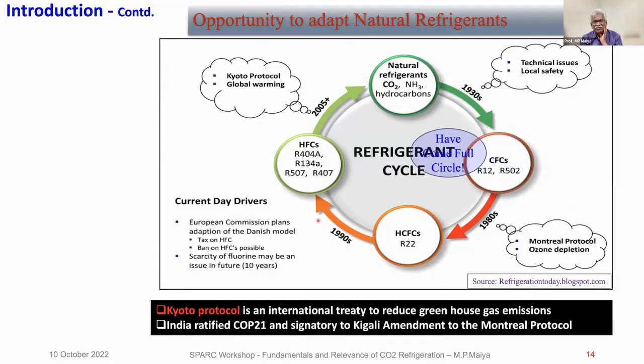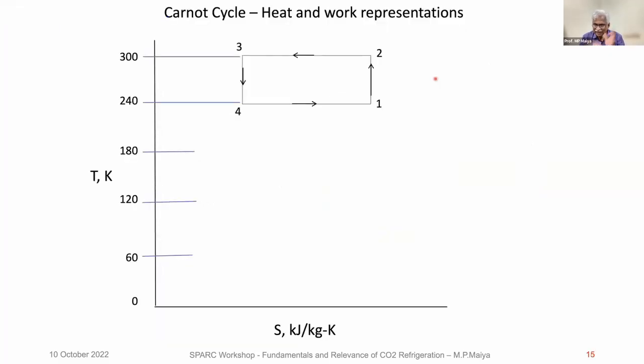So we started with natural refrigerants long back. At that time, you used whatever works. The health or safety issues were not considered. Then safety issues came, then ozone depletion, then global warming. Then you have always come in a full circle. Why not have a frog leap to natural refrigerants again? That is the introduction. We need to go back to natural refrigerants, in particular to carbon dioxide. Can we frog leap, go straight without HFOs?